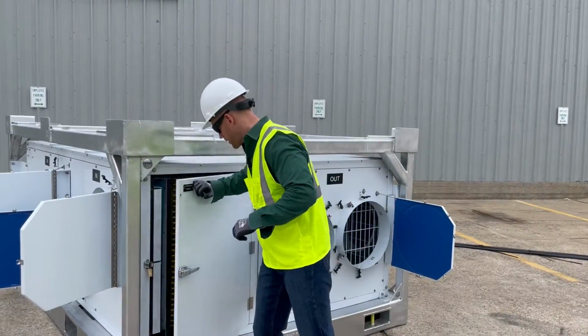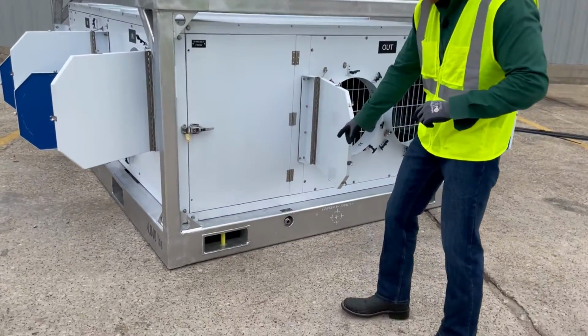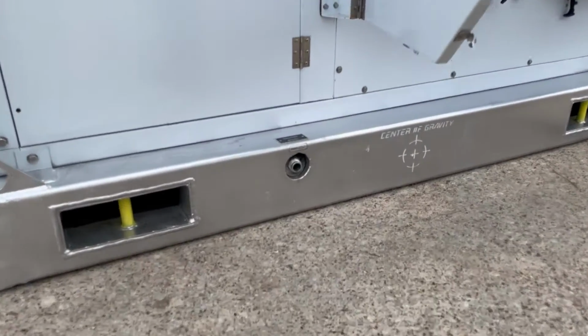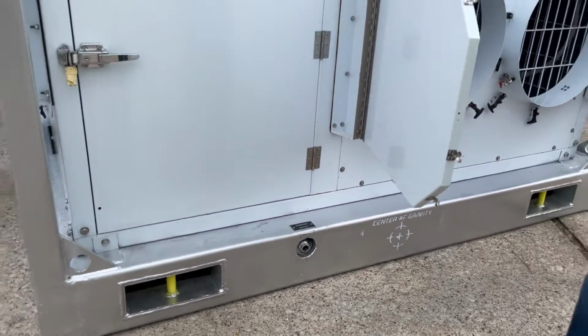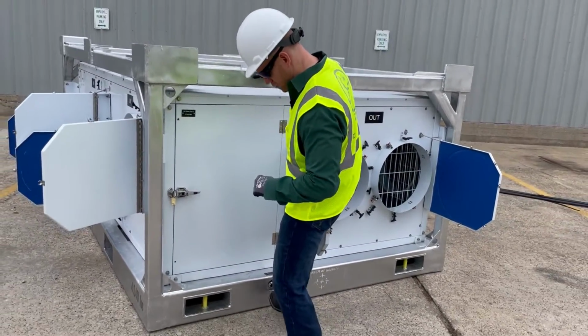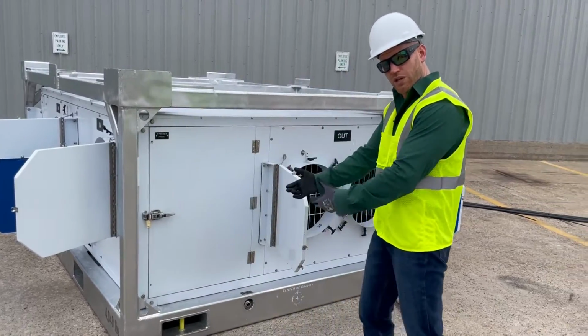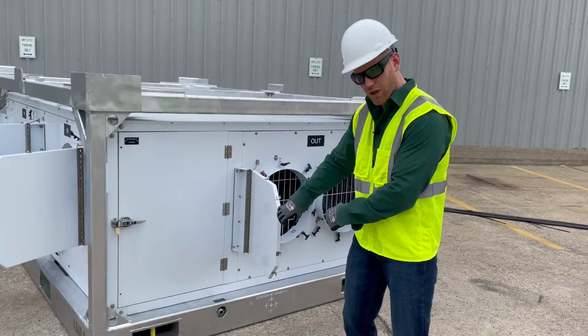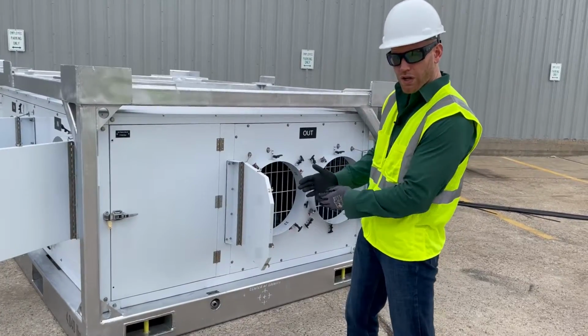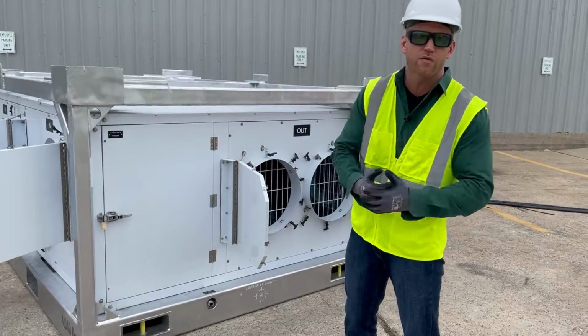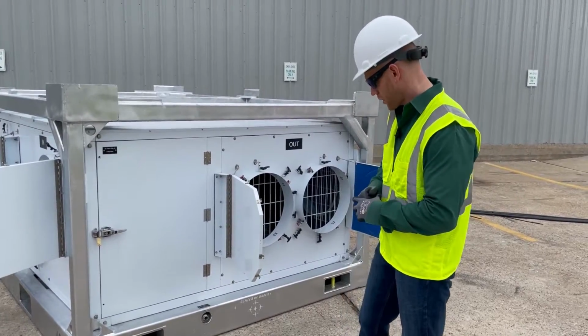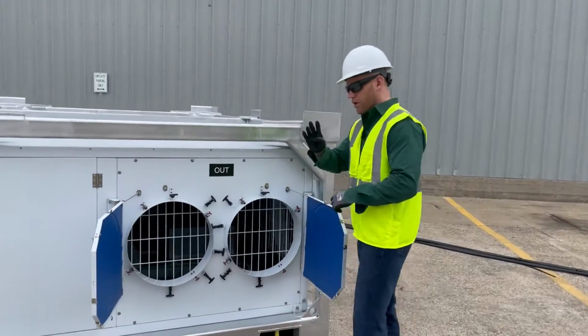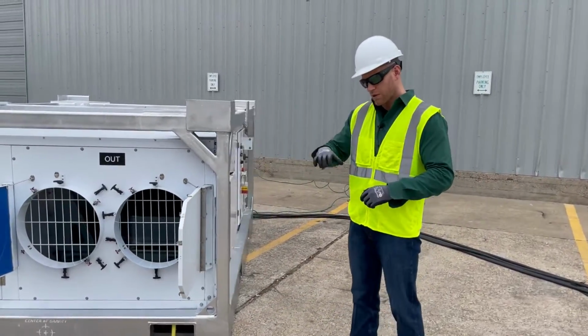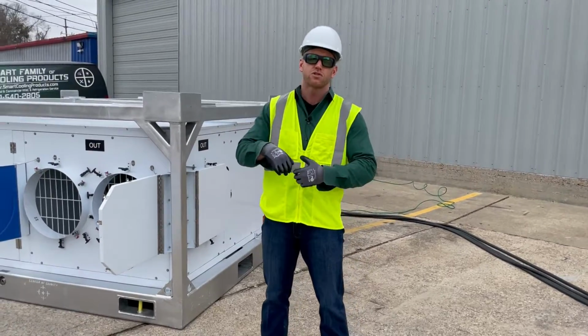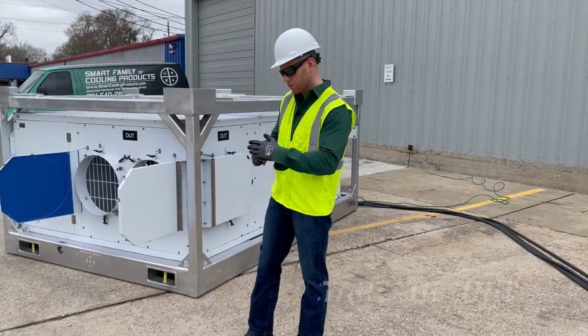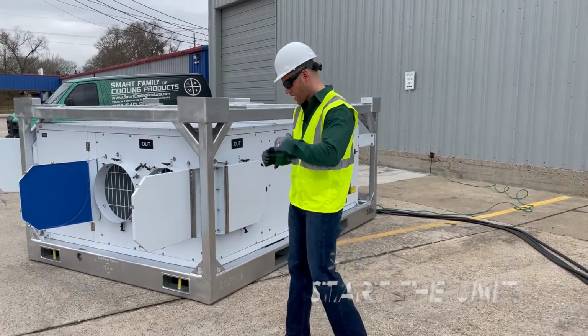As we're looking at the drain pan, we could see the drain at the bottom there, and then we actually have a condensate outlet or drain outlet connection. Our particular connection is normally inside the base so that it's protected from damage. If this was on a job site, after I inspected the drain pan, I would typically hook up my condensate lines if I didn't want to pool water where the unit was and direct that to a drain or wherever I wanted that condensate to pool. Okay? So we've gone through our normal 4 startup steps. The 5th and final step is actually going through and starting up the package. So let me walk you task by task through everything we're going to do to go ahead and start up the package.